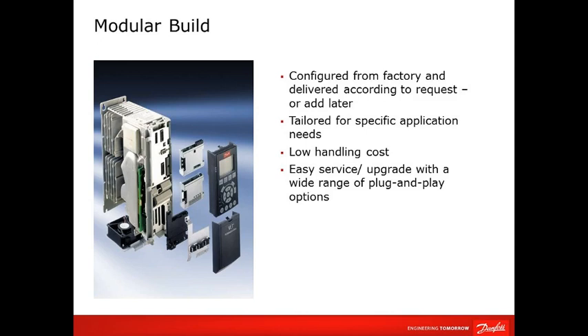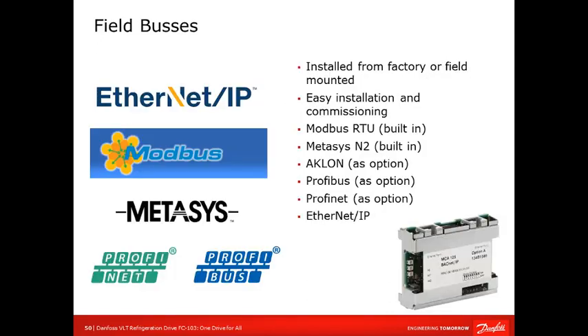There's a card right behind that HMI, or what we call the local control panel, that your customer can actually buy and install and plug right in. So the advantage you have is that even if the control changes in the future and people go more to field bus, for example, you don't have to replace the old drive. It's just an option card that you can upgrade and plug right in. So again, really plug and play, and it makes it really easy for you as things change in the future.